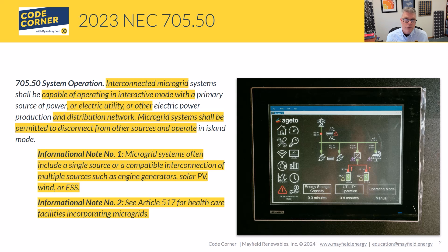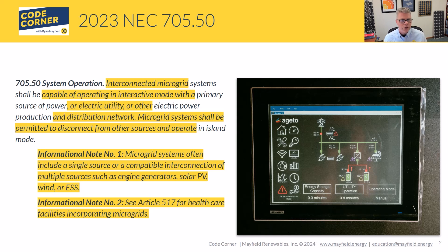Section 705.50 is where you'll find the start of talking about microgrid systems in relation to Article 705, which covers the interconnection of power production sources. There are some changes in the language from 2020. We have these interconnected microgrid systems — systems that are interconnecting with a utility, capable of operating in interactive mode with a primary source of power or electric utility. Microgrid systems shall be permitted to disconnect from other sources and operate in island mode.